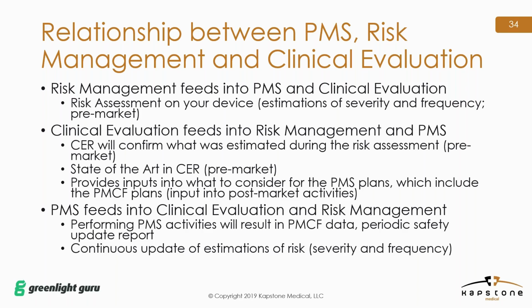You're establishing the state of the art in your clinical evaluation report, and that information is provided as an input into what you need to consider for your post-market surveillance plan for a specific device. And that post-market surveillance plan includes the post-market clinical follow-up plan. So really, the pre-market clinical evaluation is being used as an input into some post-market activities. And then, of course, post-market surveillance feeds into clinical evaluation and risk management.